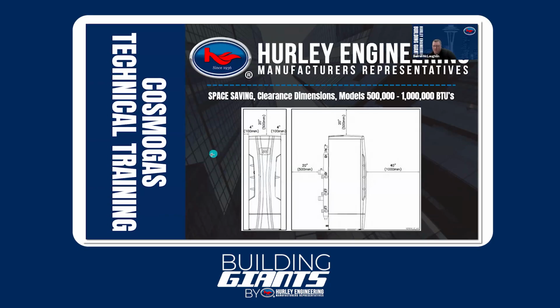Okay, clearances. So common clearances, it's only 4 inches clearance to combustibles on the sides. When you see larger clearances for the top, bottom, and rear, those are service clearances. So those are for ease of access, not for combustibles. Your combustible clearance is only 4 inches.